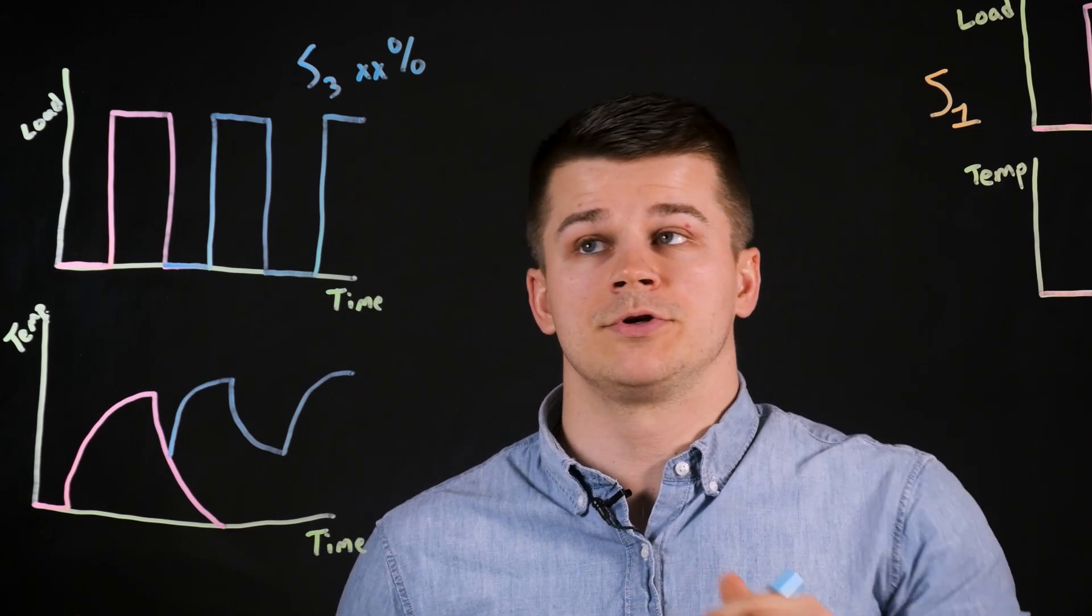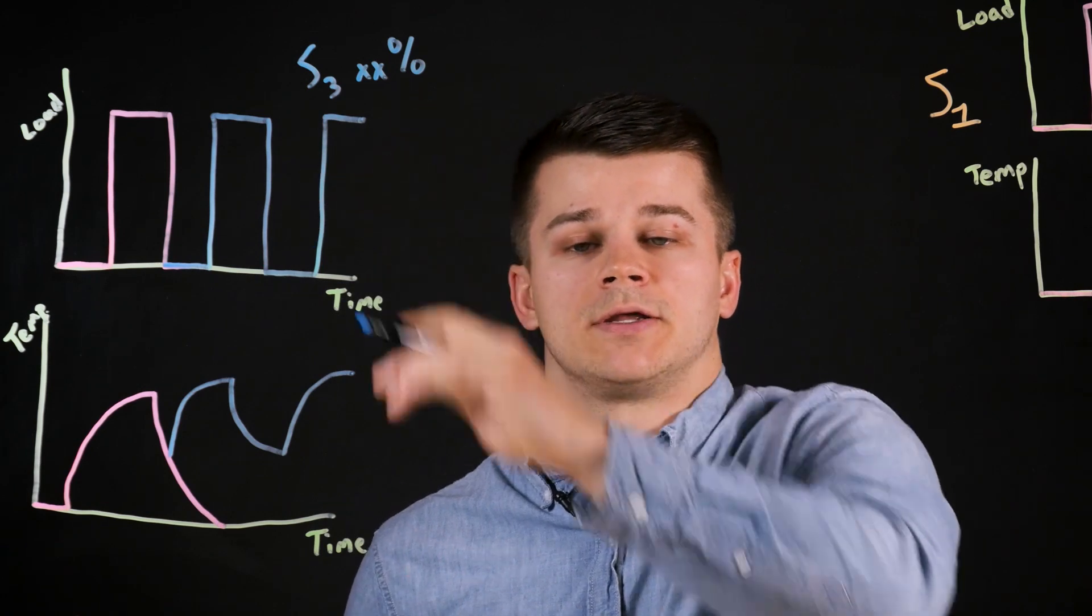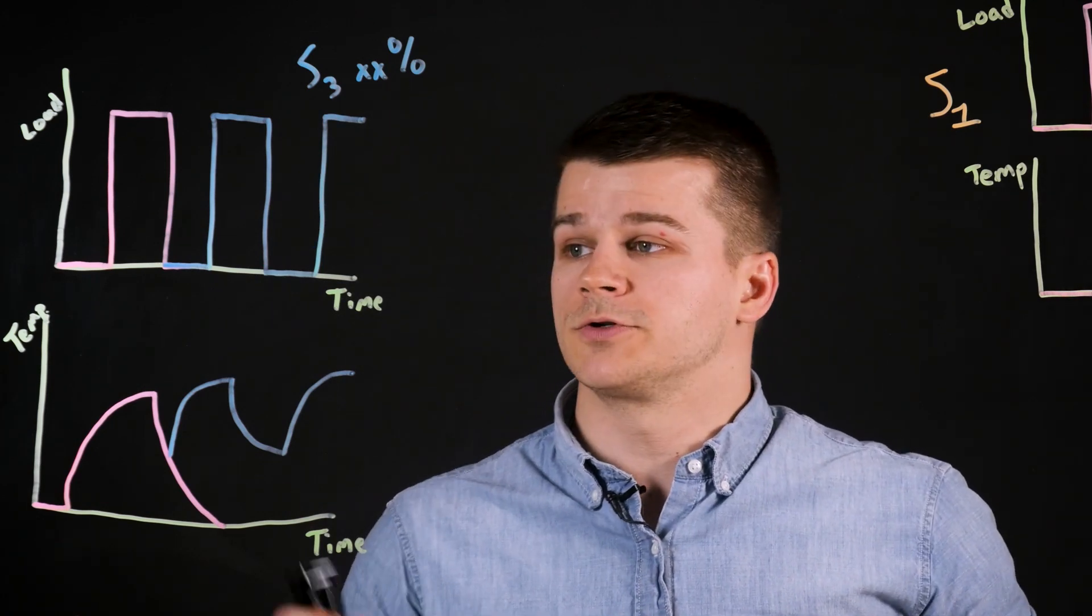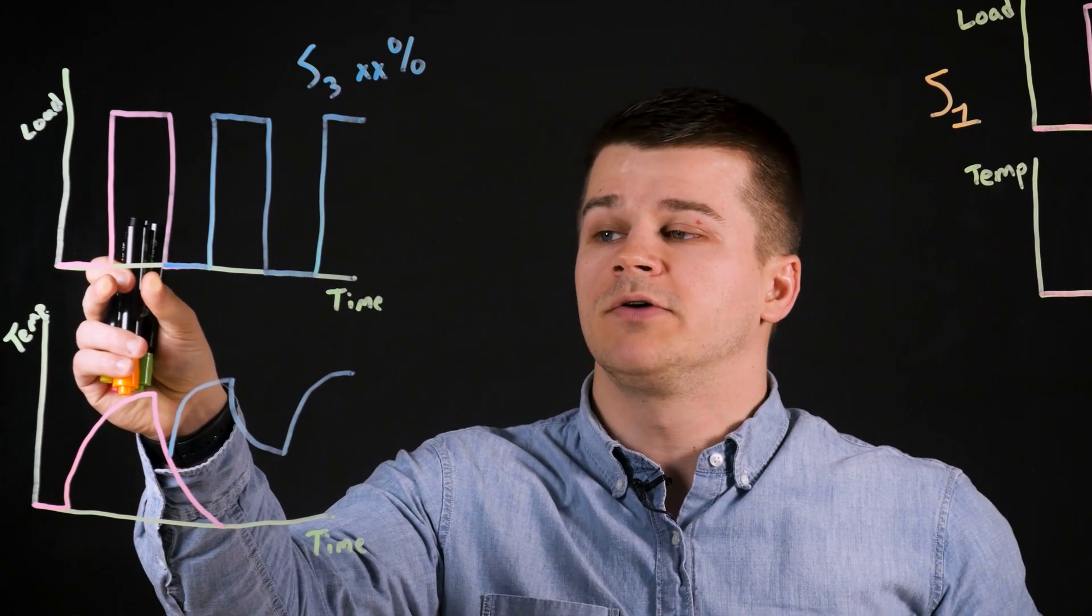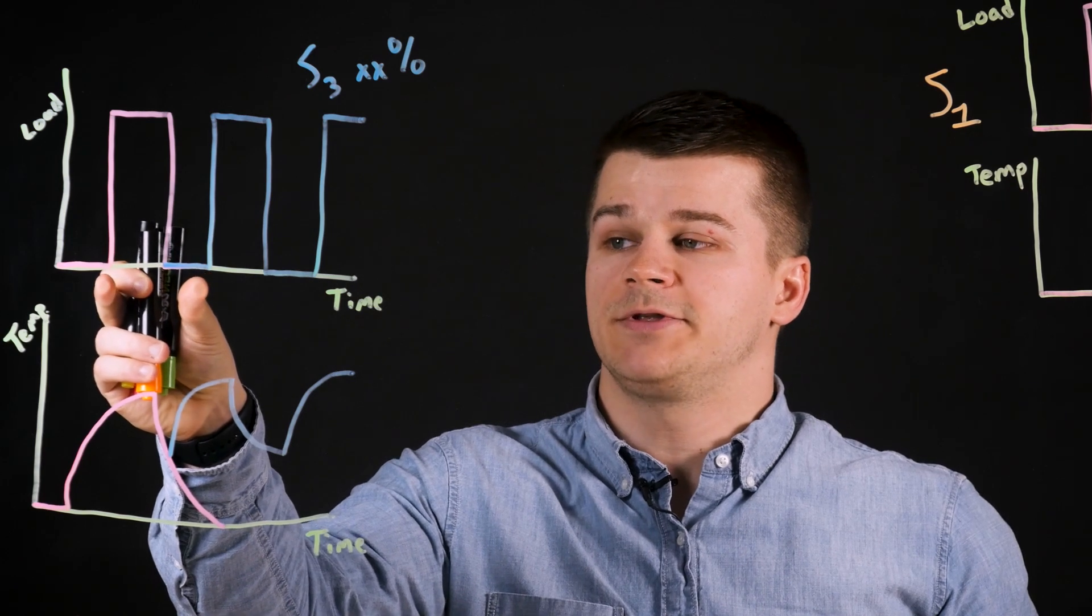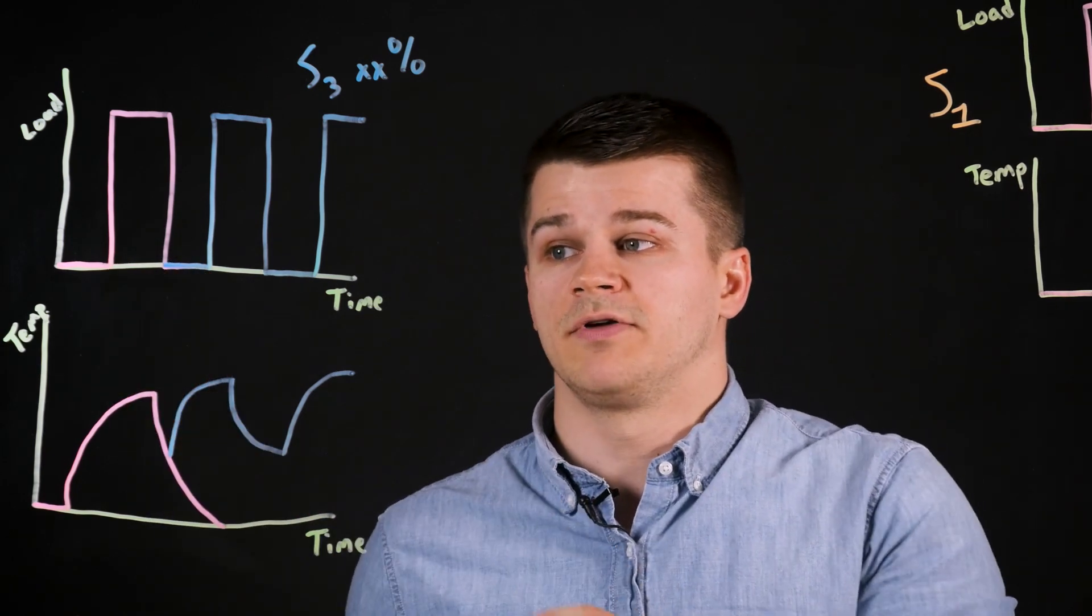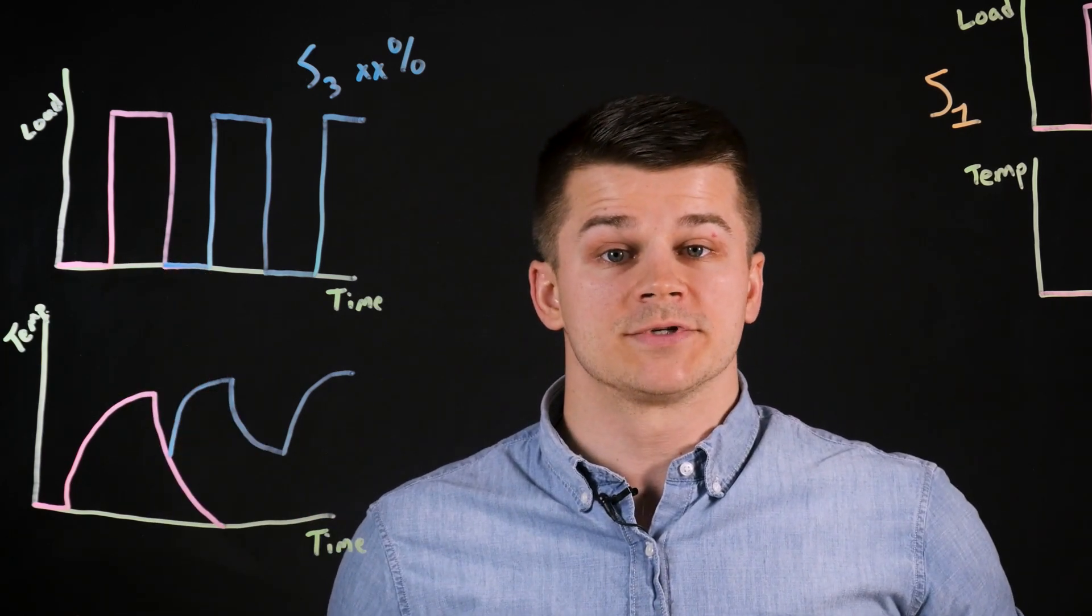Intermittent periodic duty is referred to as S3 followed by a percentage. The percentage refers to the amount of time under load divided by the total amount of time of the cycle. So in this graph, it would be roughly 50% duty.